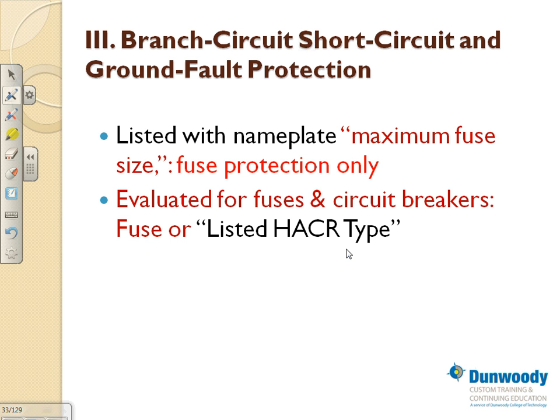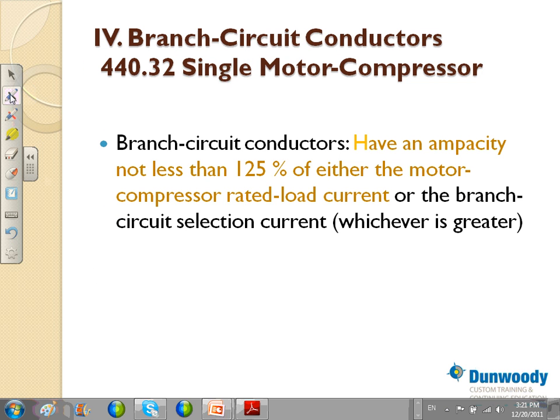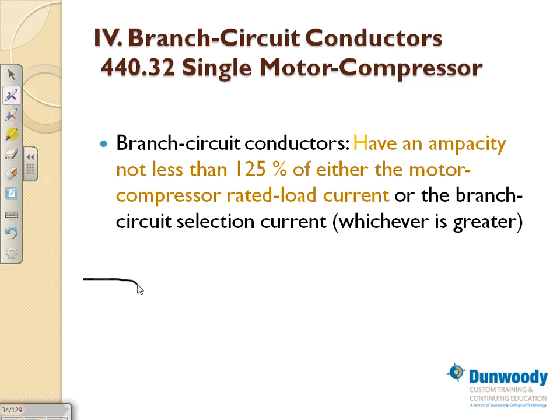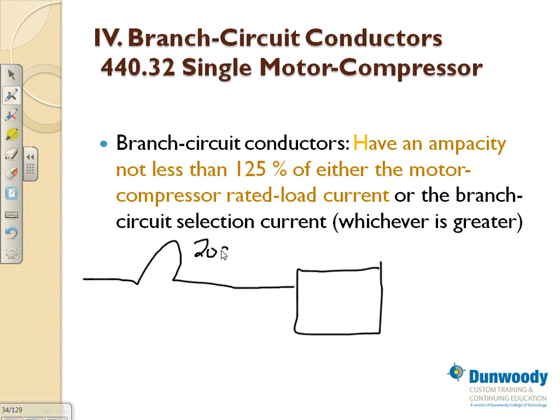And the reason for this is the way the HVAC equipment consumes power and the impact on the electrical system. If the circuit is not rated HACR, it could nuisance trip and not protect you properly. So if I have equipment like this, my friend, here's my equipment, coming off a circuit breaker. Here's my HVAC right in here. I can have a 200 amp circuit breaker here, and it has to be HACR.